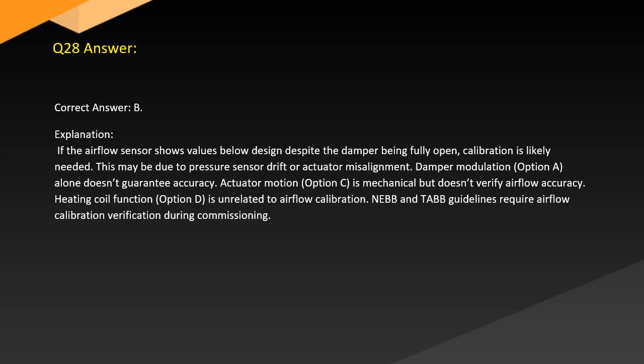Answer. Correct answer: B. Explanation. If the airflow sensor shows values below design despite the damper being fully open, calibration is likely needed. This may be due to pressure sensor drift or actuator misalignment. Damper modulation, option A, alone doesn't guarantee accuracy. Actuator motion, option C, is mechanical but doesn't verify airflow accuracy. Heating coil function, option D, is unrelated to airflow calibration. NEBB and TAB guidelines require airflow calibration verification during commissioning.